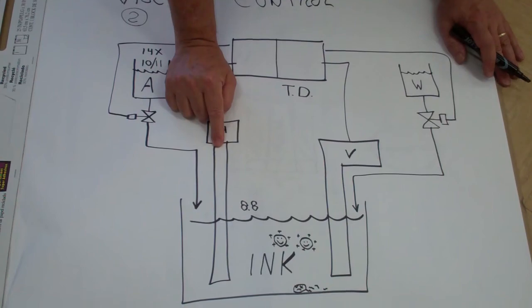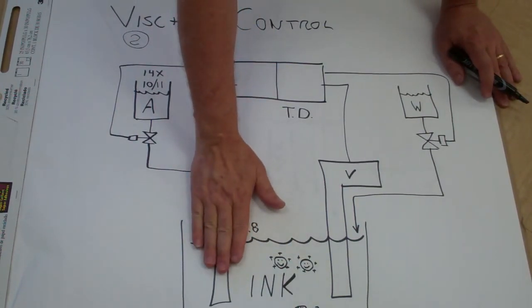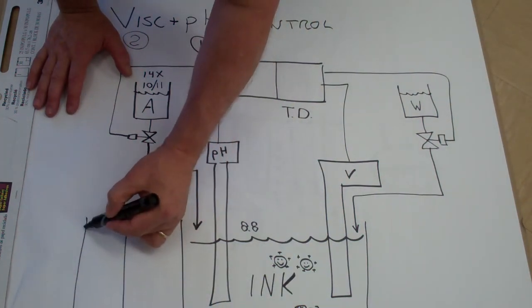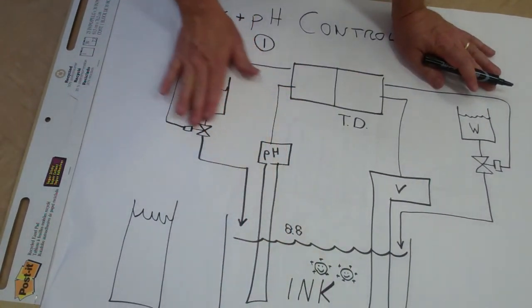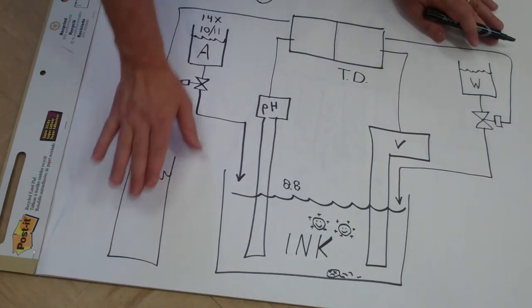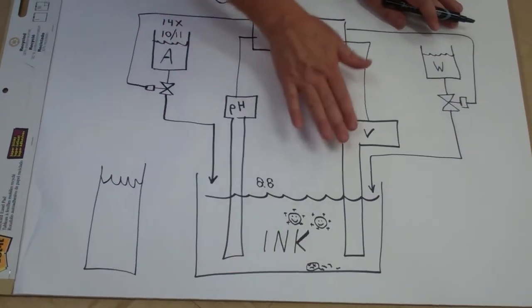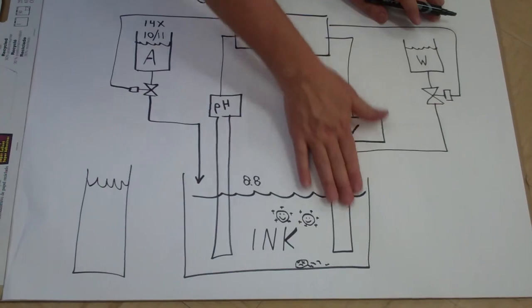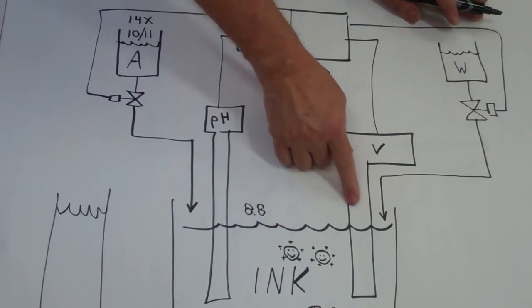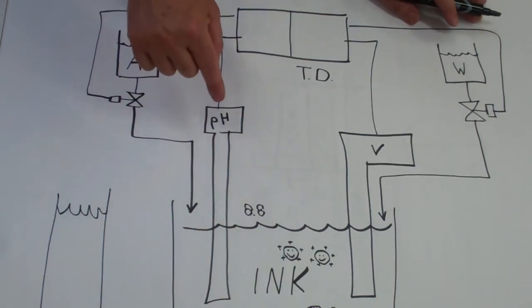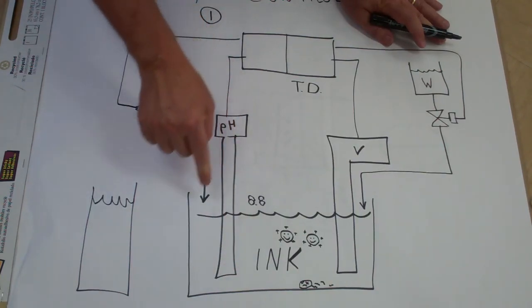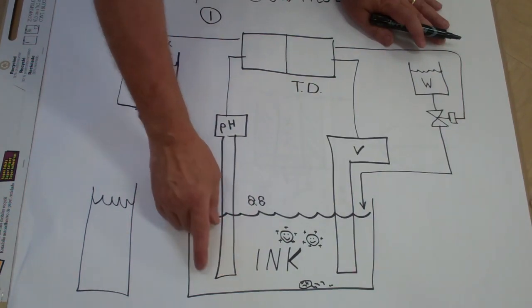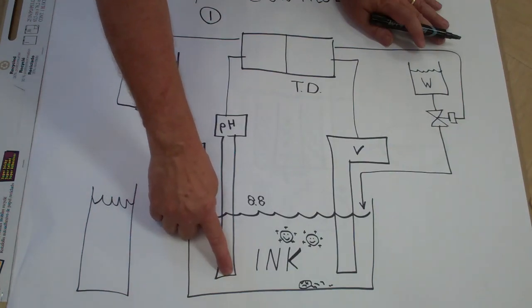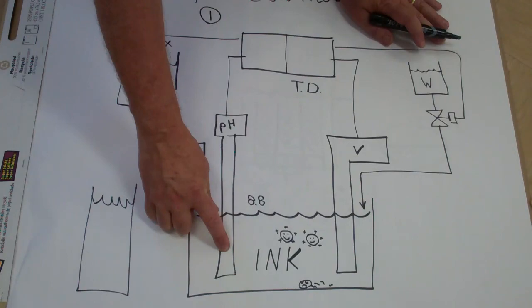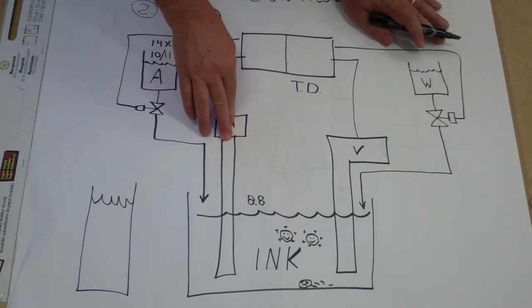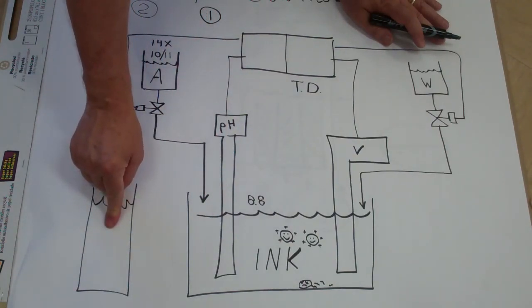Whether you're in tank or in a line. If you're in a tank and the job is done, take the probe out. Have some standpipe somewhere with some fluid. Probe comes out, goes in the standpipe. Keep it wet. Change the ink, put it back in. Norcross viscometers can sit here and get dry, and they can begin functioning when they get wet again. They're mechanical. This has the glass tip. It's inherent in every pH sensor in the world. You have to keep that end wet. If you don't, or if you have sludge that comes along and covers the junction, you're going to get incorrect readings. pH is a slow-moving parameter. It changes slowly. So always wet, always clean.